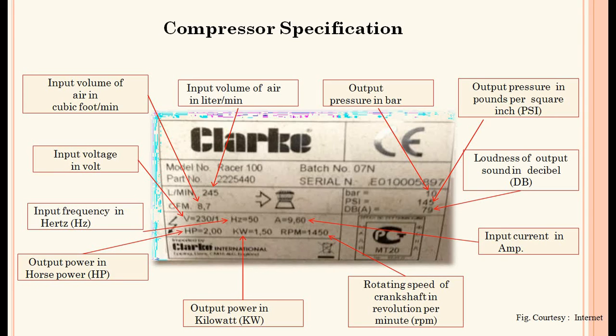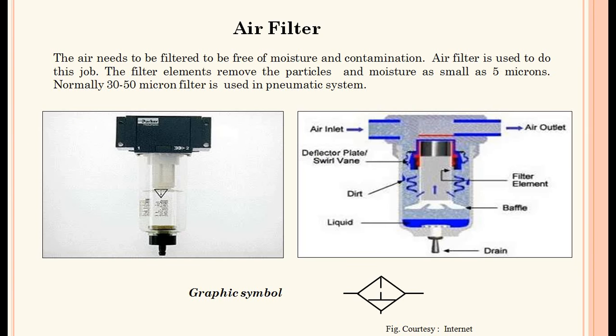Compressor specifications are shown in this slide. The next component is the air filter — air needs to be filtered to be free from moisture and contamination. The air filter removes particles and moisture as small as 5 microns; a normal 30 to 50 micron filter is used in a pneumatic system. The picture, cut section, and symbol are all shown.